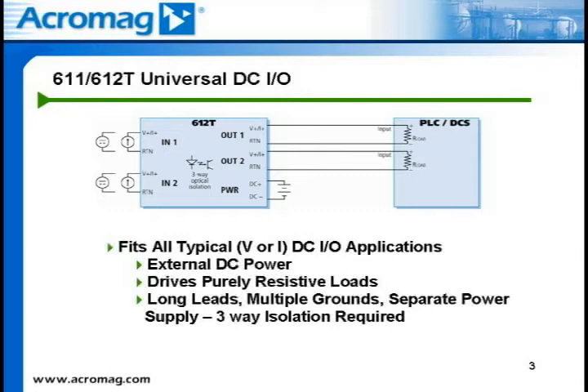The 611 and 612T isolated transmitter can also be used for boosting the signal in applications for long-distance cable runs or high-loop impedance applications. In long cable runs, the cable resistance can add a significant load to your output loop. Or, where many devices are installed on a loop, the total impedance is greater than what the field device can drive. A signal booster is required to overcome the load impedance.